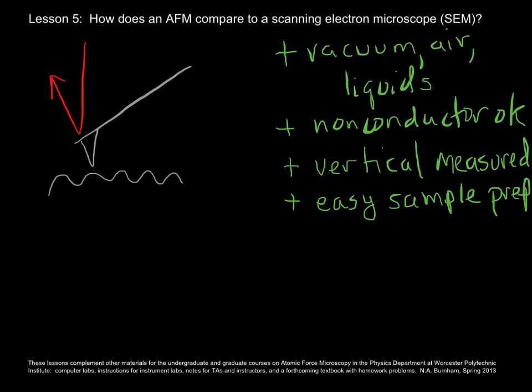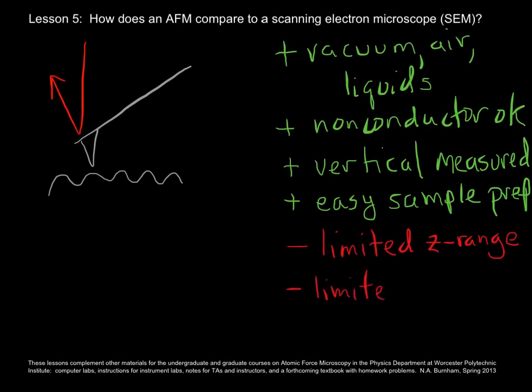What are the disadvantages? There's a limited Z range — most AFM scanners cannot accommodate height changes of more than a few microns. Also, the lowest magnification — when you want to see all of the sample — is limited to maybe 100 by 100 microns at a time, whereas in SEM you can see up to about a centimeter of your sample. So many AFMs use an optical microscope to see where the cantilever is over the sample, which adds some complications and expense.